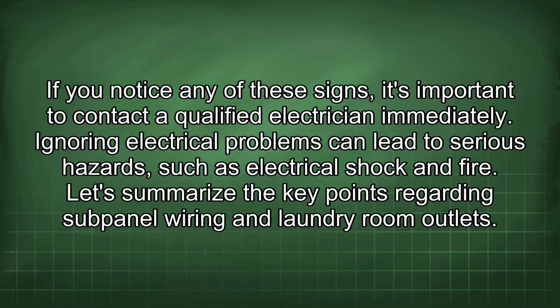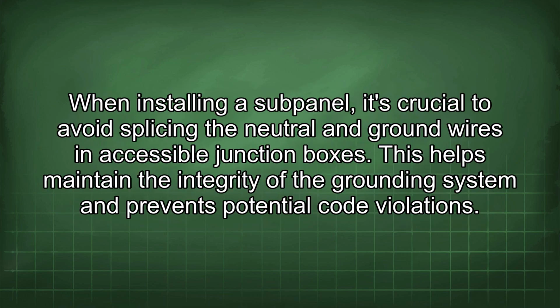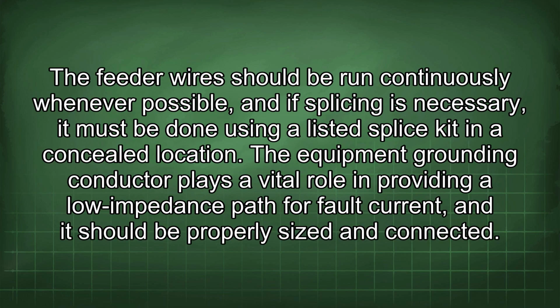Let's summarize the key points regarding subpanel wiring and laundry room outlets. When installing a subpanel, it's crucial to avoid splicing the neutral and ground wires in accessible junction boxes. This helps maintain the integrity of the grounding system and prevents potential code violations. The feeder wires should be run continuously whenever possible, and if splicing is necessary, it must be done using a listed splice kit in a concealed location. The equipment grounding conductor plays a vital role in providing a low impedance path for fault current, and it should be properly sized and connected.